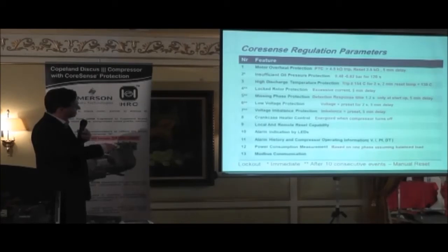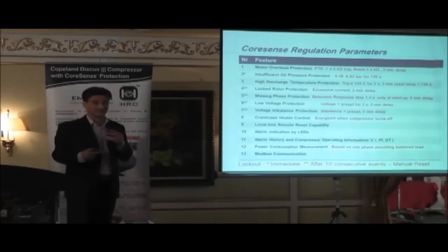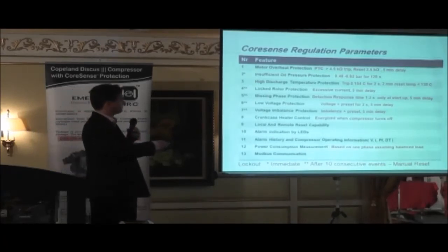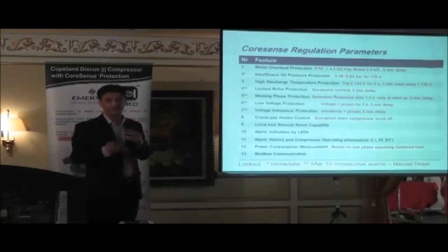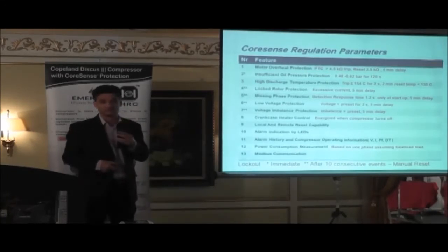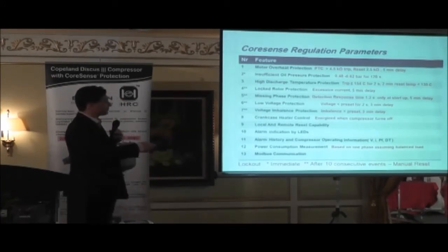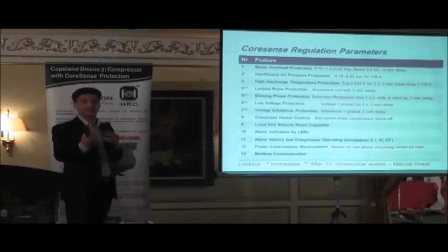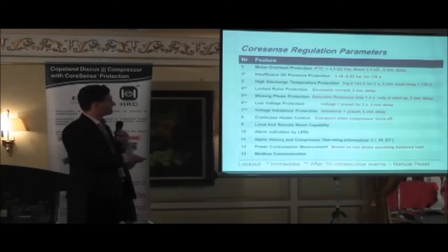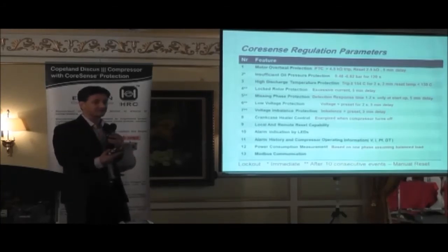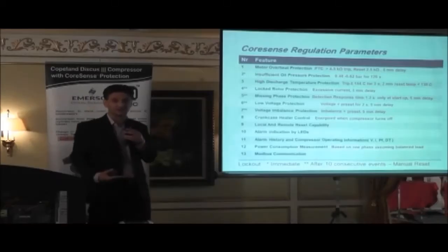Items 4, 5, 6 and 7 all relate to the sensor module. Okay? So, if the compressor starts up and it goes into lock rotor, it will trip and there will be a 5-minute delay and it will try and start again. The same goes for missing phase. Every time the compressor starts up, if one of the phases is missing, it switches off the compressor, waits 5 minutes, and will then try and restart the compressor again.